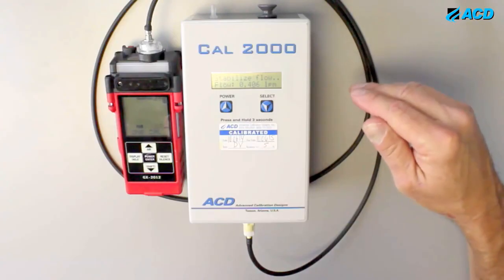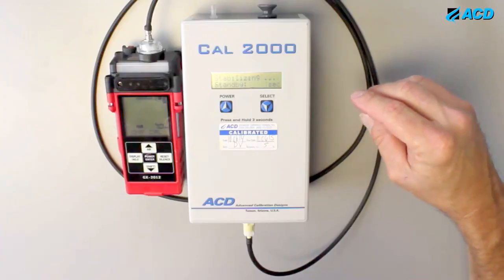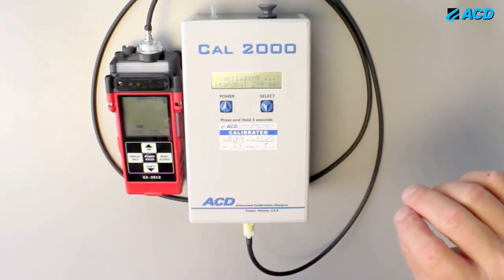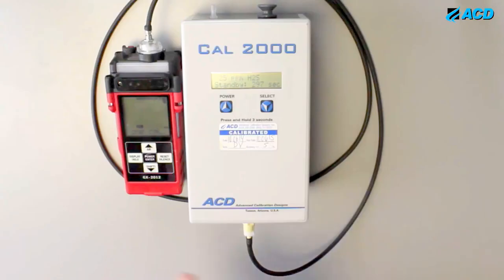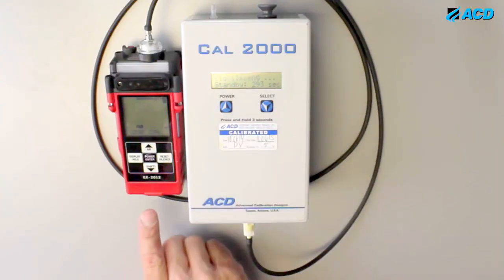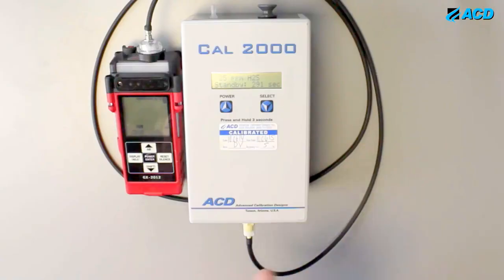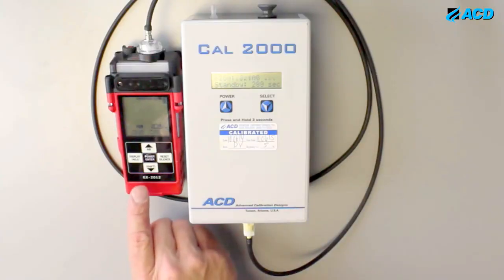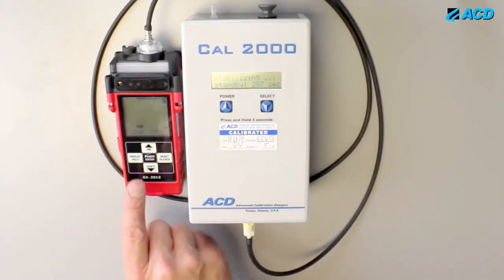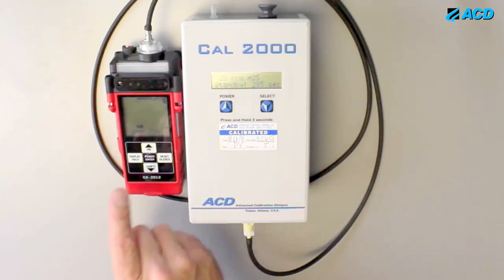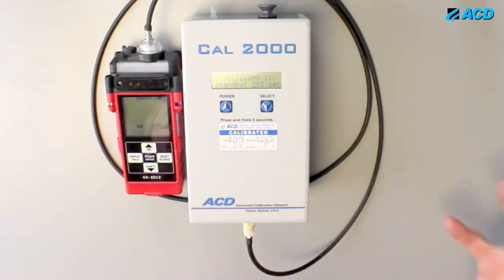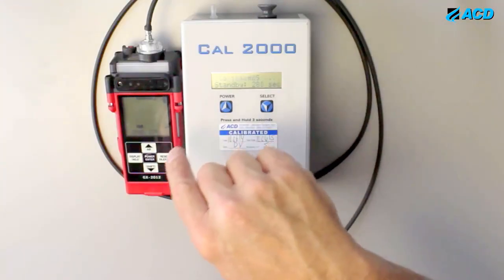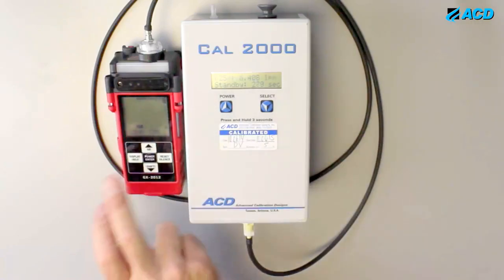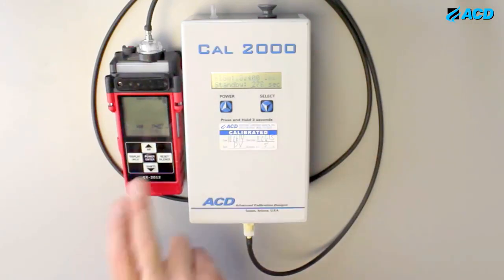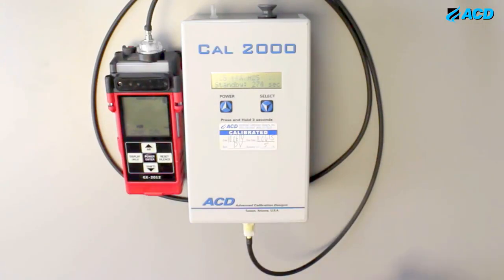It's checking the flow to make sure the flow is okay. And when the flow sensor likes it, it starts to stabilize at 25 parts per million. Now again, the first time, I've got to let this thing stabilize at 25 parts per million before I calibrate my gas detector, and I'm not going to go through that whole thing with you, but you can see it. It's coming up 11, 12, 12 and a half, because we're passing current and it's stabilizing, going through the hose into the unit. And now, if I wanted to, I could calibrate this sample draw unit.